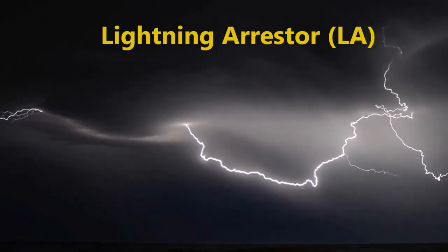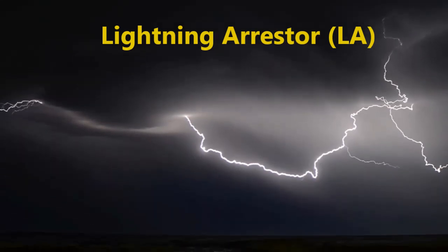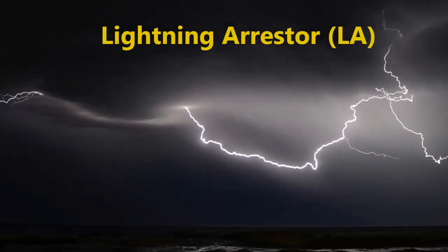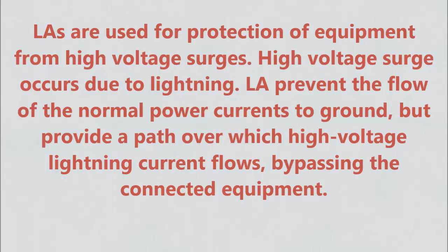Sixth, lightning arrestors, also called LA. Lightning arrestors are used for protection of equipment from high voltage surges. High voltage surges occur due to lightning. Lightning arrestors prevent the flow of normal power currents to ground, but provide a path over which high voltage lightning current flows, bypassing the connected equipment.